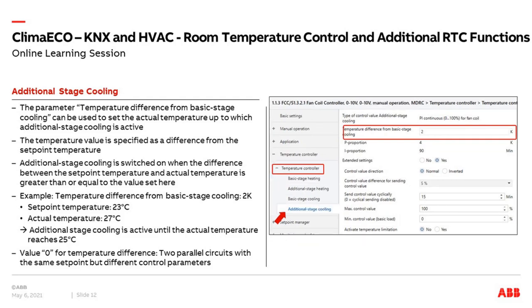For cooling, it's not really different. You can define an individual gap between set point and room temperature. For example, with a set point of 23 degrees, if the actual temperature is more than 25, it's too warm and you start the additional cooling stage. You can also adjust this difference to zero — then there's no difference threshold and the additional stage heating or cooling is always active, so you have two control solutions running in parallel all the time. This is also possible if it makes sense.